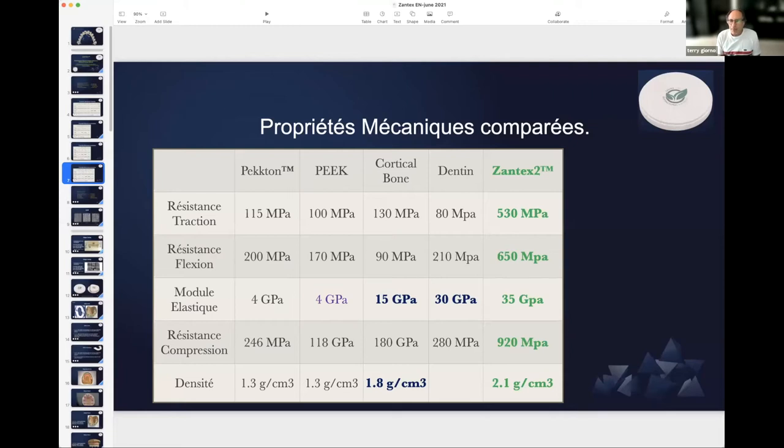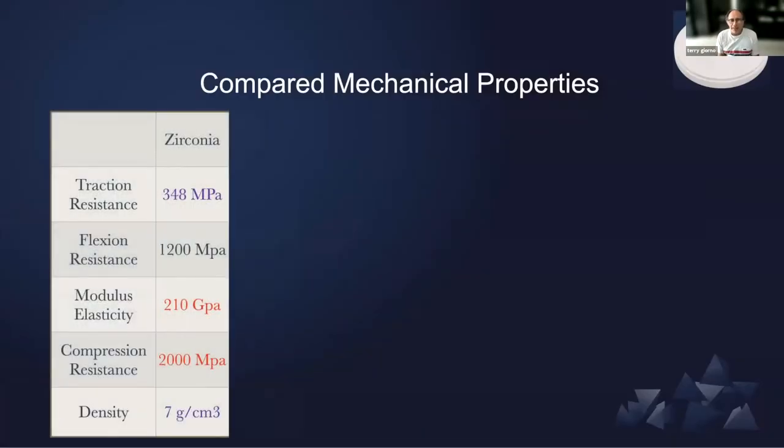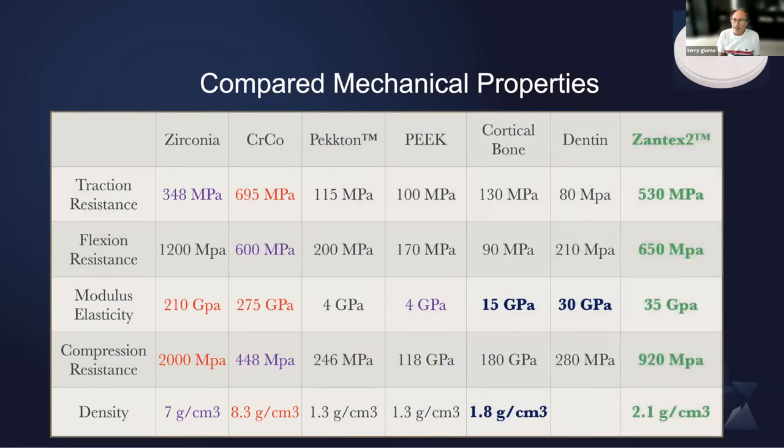We are going through the mechanical properties. We went to compare mechanical properties — here we have all the different materials to compare to. The Zantex2 on the far right column shows that the mechanical properties are really perfect, that's all you need. And as a bonus, the density is only about two. So compared to zirconia or to chrome cobalt, you will have very strong material with three or four times less weight for an equal structure.